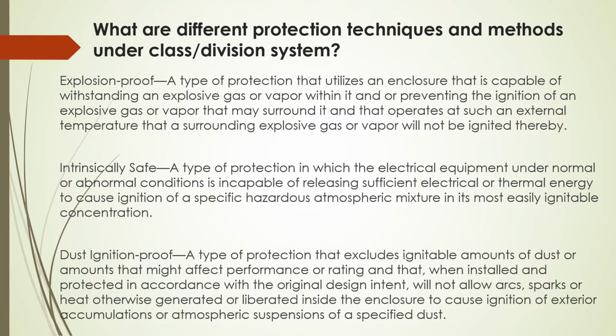Intrinsically safe, a type of protection in which electrical equipment under normal or abnormal condition is incapable of releasing sufficient electrical or thermal energy to cause ignition of specific hazardous atmosphere mixture in its most easily ignitable concentration.